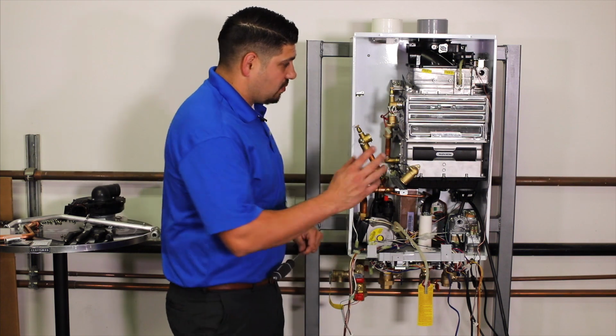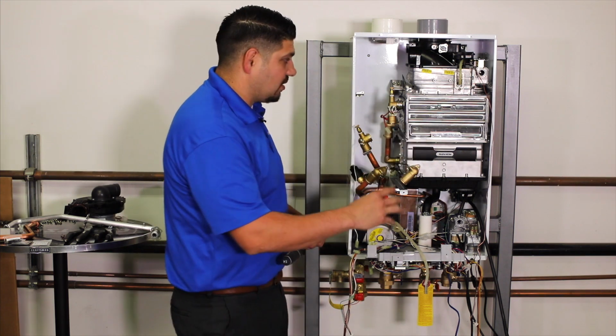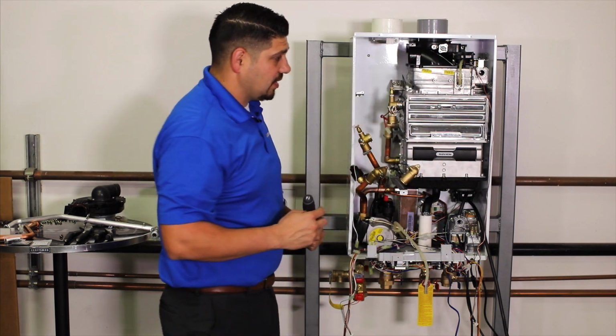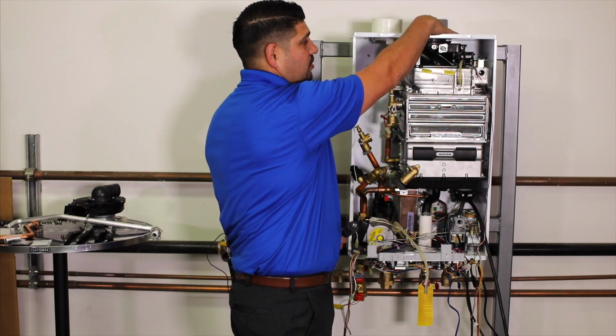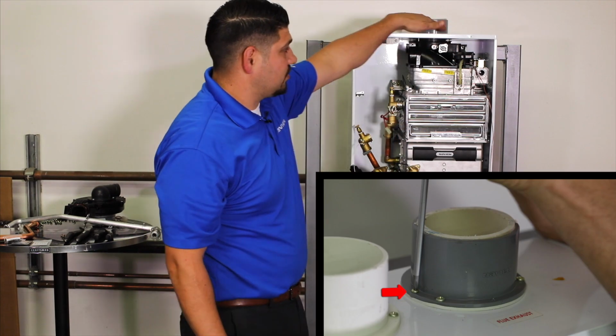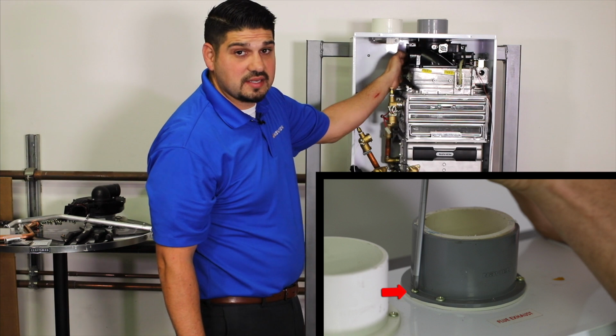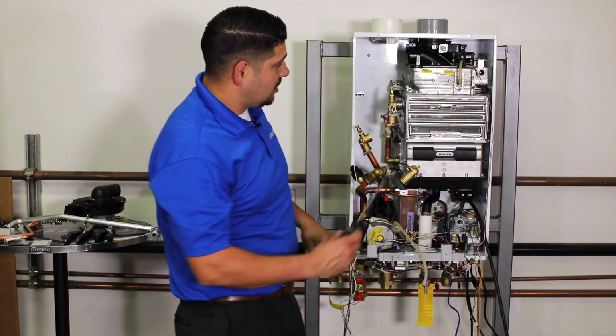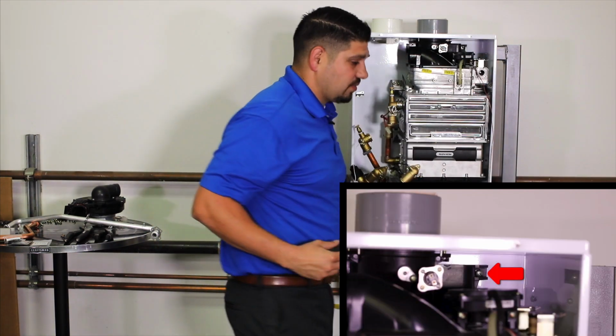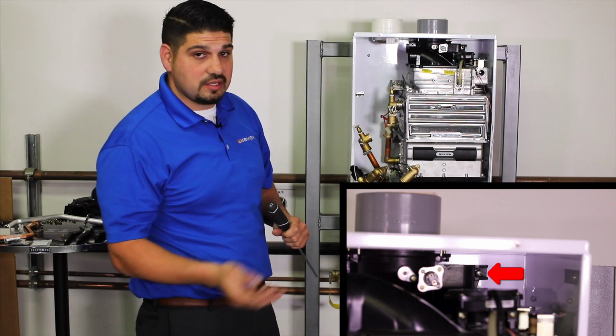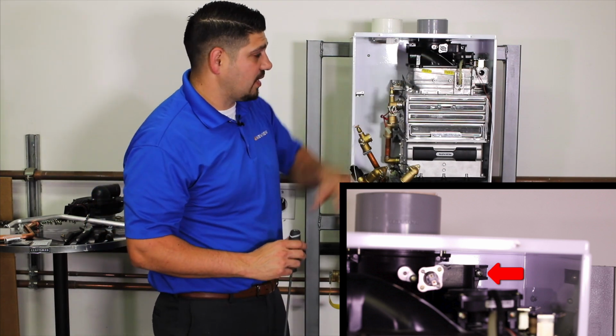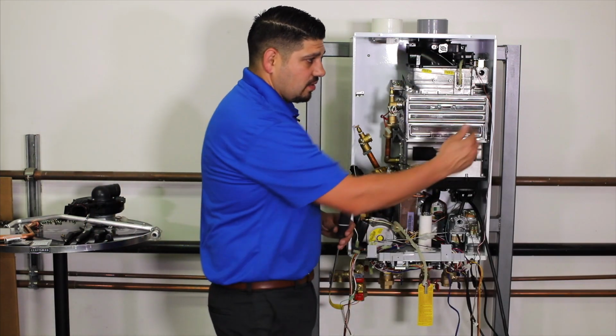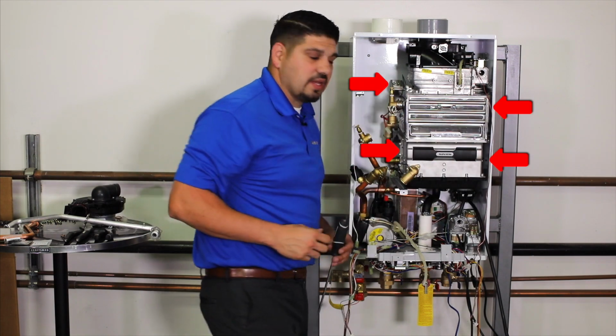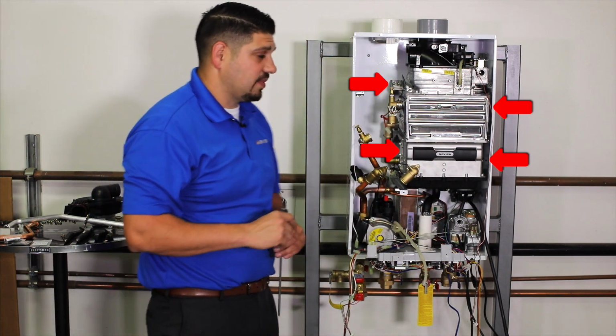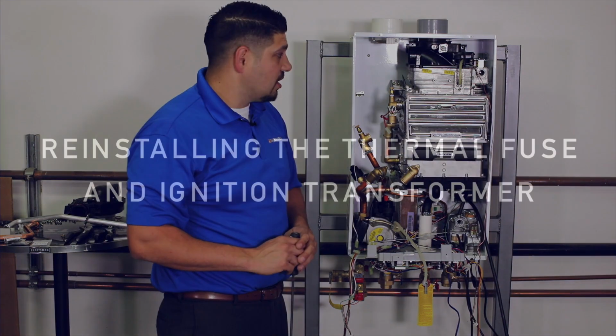We've taken a liberty. We put the heat exchanger right back in. All you did was slide it right into the collar. There are two Phillips screws we tightened down that connect the exhaust duct to your collar. There's one Phillips screw that connects your exhaust duct to your cabinet, which is right there in that corner. And then there are 4 mounting brackets. We lined those holes up and put those screws in, and now your heat exchanger is where it belongs.